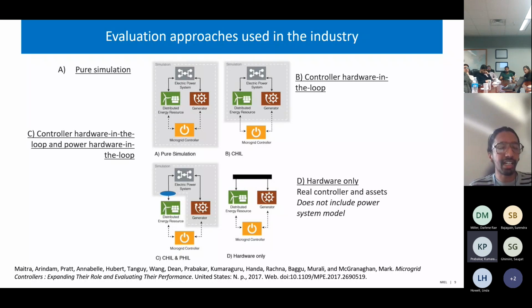So we go into controller hardware in the loop, where you're able to run the power system or other things in real-time simulation, and then exchange information between that and the controls. That can be through analog or digital input/output, or even actual communications like TCP/IP, PMU communications, DNP3, or 61850. Those are all commercially available.